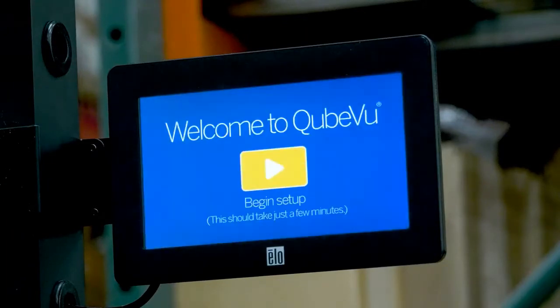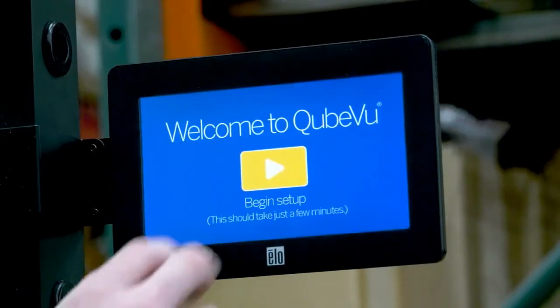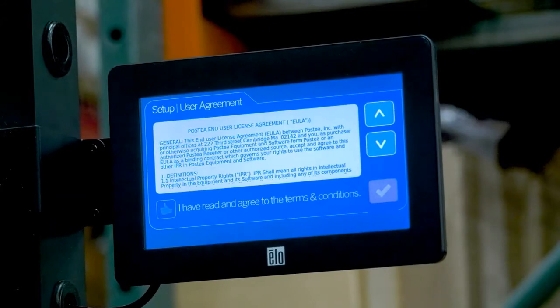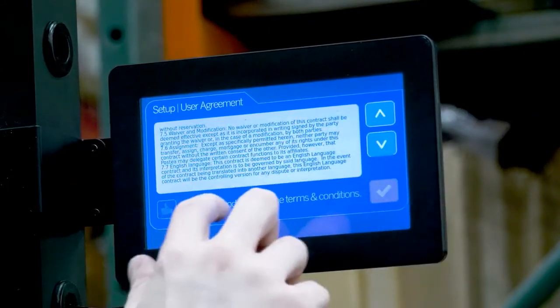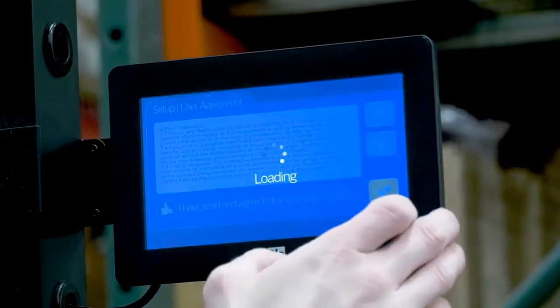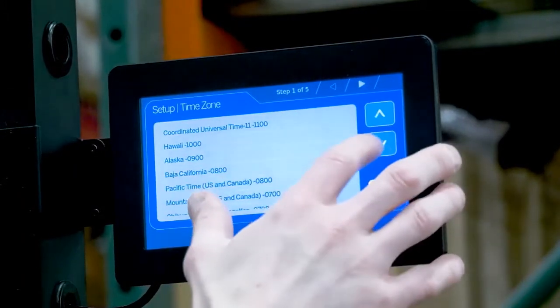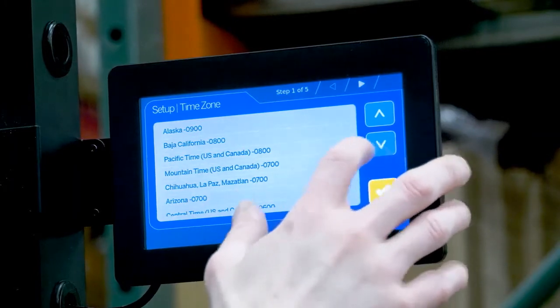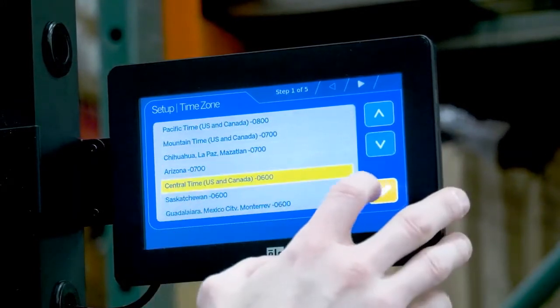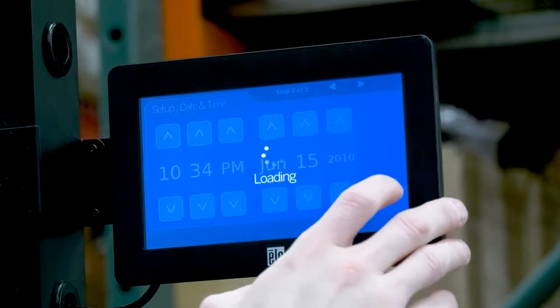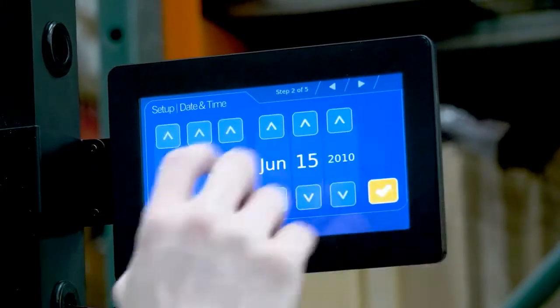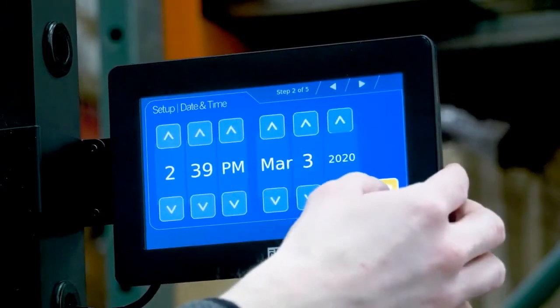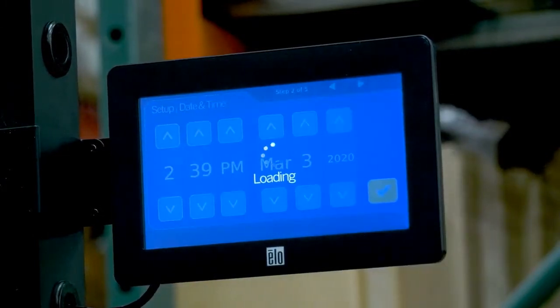The setup wizard will display during initial power up. Press Begin Setup. Read the user agreement, confirm, and press the check mark to proceed. Set the appropriate time zone, then press the check mark to set time and date. When complete, press the check mark. Select the base type of the iDimension Plus.